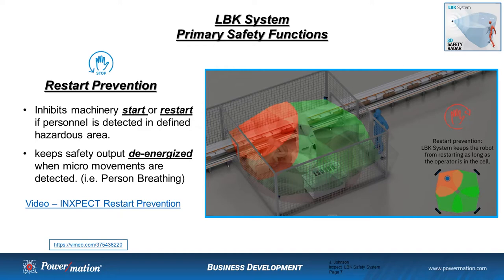Restart prevention is designed to inhibit a machine start or even a restart if personnel is detected in the defined hazardous area. It keeps the safety output de-energized when micro-movements are detected — this system can actually detect our ribcage expanding. InXpect did a really nice job creating a simulation video on how this restart prevention could be applied in an application.